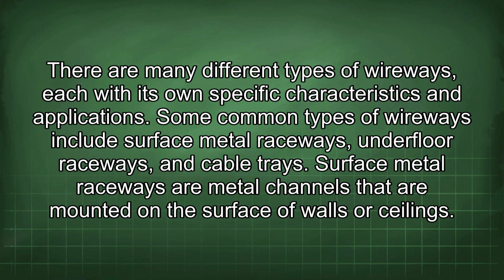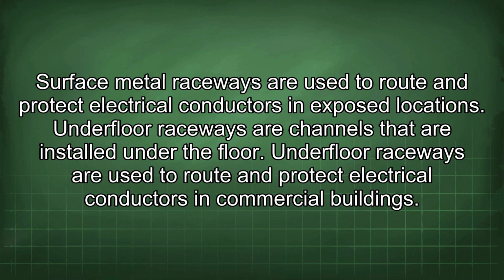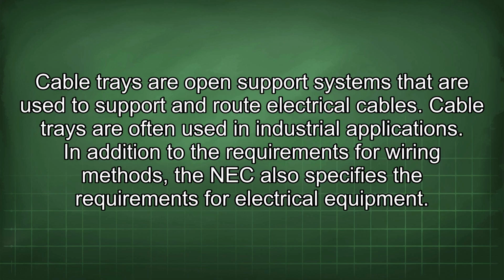Surface metal raceways are metal channels that are mounted on the surface of walls or ceilings. Surface metal raceways are used to route and protect electrical conductors in exposed locations. Underfloor raceways are channels that are installed under the floor. Underfloor raceways are used to route and protect electrical conductors in commercial buildings. Cable trays are open support systems that are used to support and route electrical cables. Cable trays are often used in industrial applications.